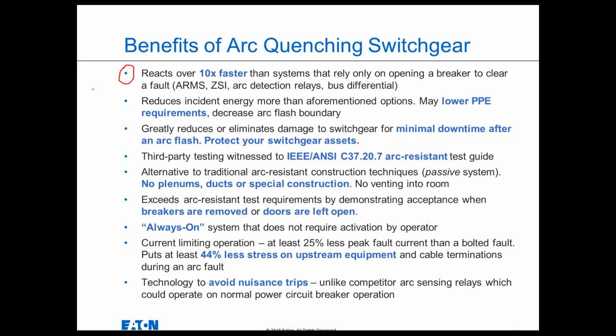Arc quenching switchgear reduces the incident energy to such a low level that the switchgear can actually pass that IEEE ANSI C37.20.7 arc resistant test guide in standard NEMA 1 construction. So that means the incident energy is so low that there's no longer a need for thicker gauge steel, 3-point latches, piano hinges, ducts, plenums, all that stuff that's required to make traditional passive arc resistant equipment arc resistant, essentially making a bomb-proof box to contain all that energy. It's no longer needed because there's such little energy emitted from the arc flash, because it's quenched so quickly that you don't need a robust enclosure to contain what little energy is released.